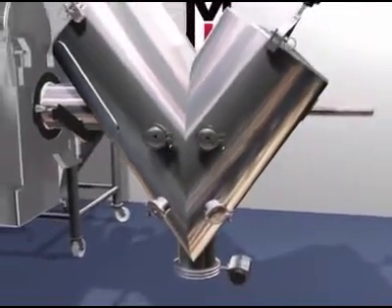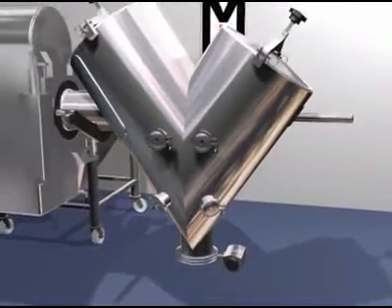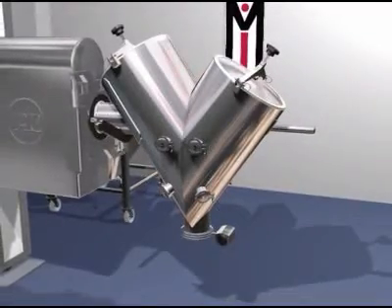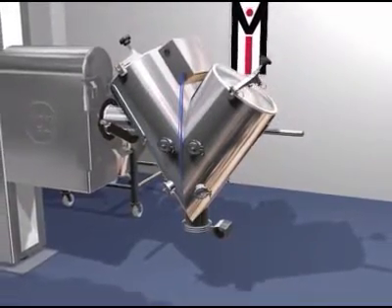Flush-mounted sensors are placed in eight positions on the periphery of a blender. The Mathis sensors operate on heat transfer principles to measure a property called effusivity. Because powders transfer heat differently, effusivity values vary based on composition.